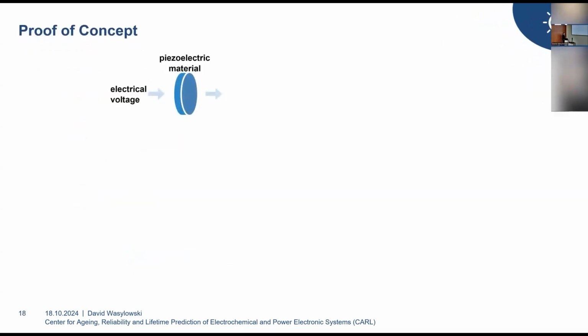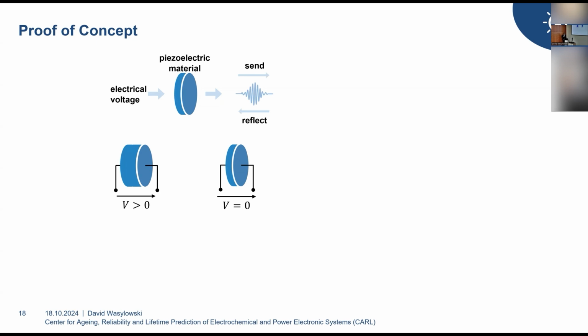In order to measure ultrasound, we first need to produce sound waves, and typically we use piezoelectric materials. These types of materials change their structure when they are in an electric field. So when you, for example, apply a positive voltage on them, they increase in thickness, but when you then suddenly disconnect this voltage, they jump back to their original size. And if you do this disconnection fast enough, the elastic properties of the material and the inertia make the material wiggle and produce this sound wave here. In practice, we use high voltage, over 100 volts, and very short pulses, less than 1 microsecond, to apply on these piezoelectric materials to produce a sound wave.